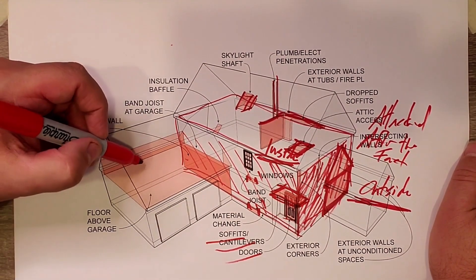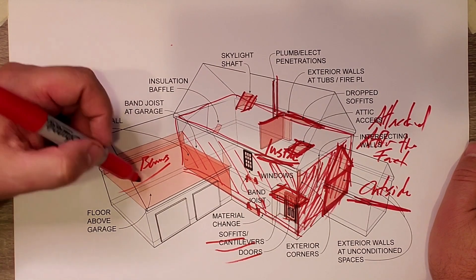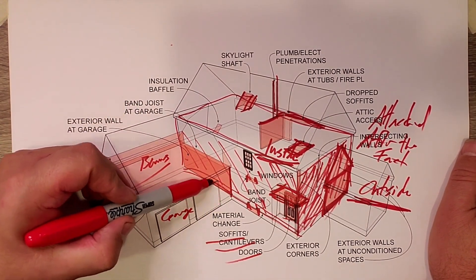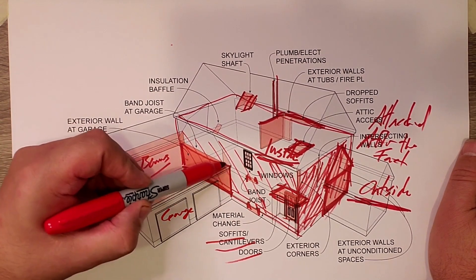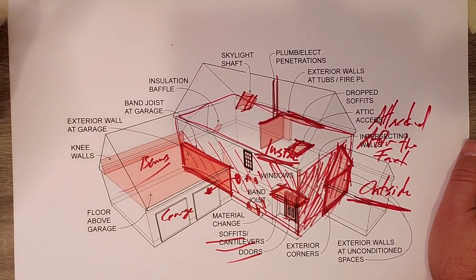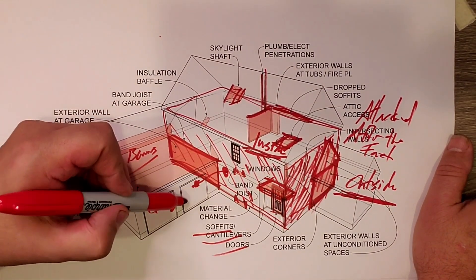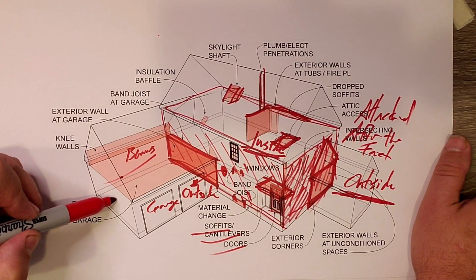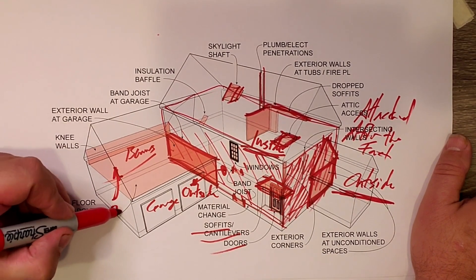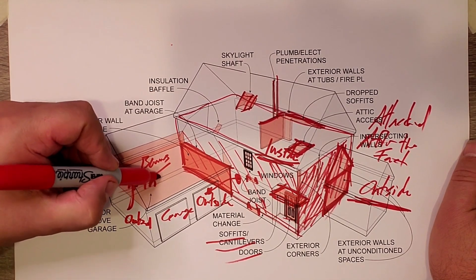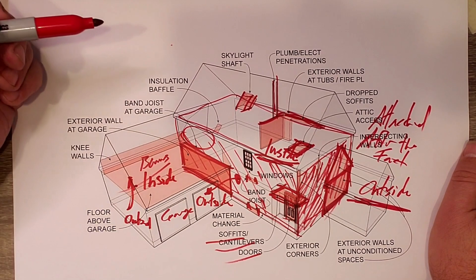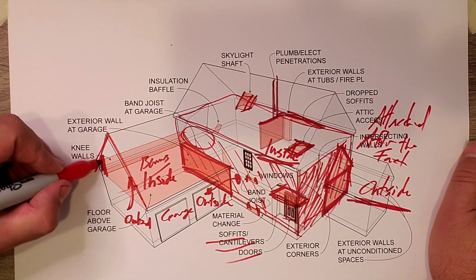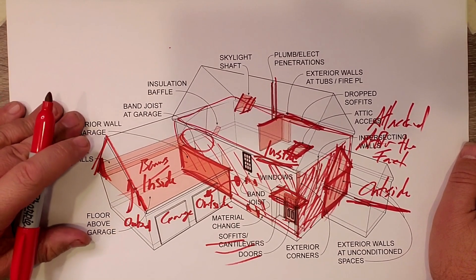One of the bigger problems is this bonus room that people love to put over the garage. The problem with that is we have an air barrier we have to maintain between the house and the garage, because the house is inside and the garage is outside. The upstairs versus the downstairs — the garage is outside, but the bonus room is inside. A lot of times this bonus room is kind of cape style, and the problem is you end up with these areas where this attic space is confused — is it outside or is it inside?